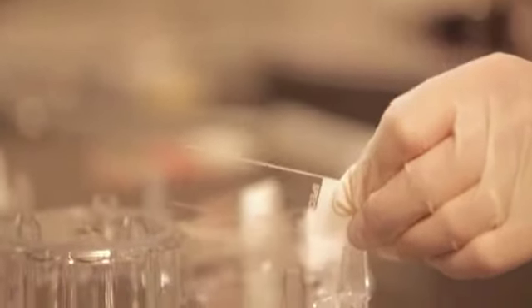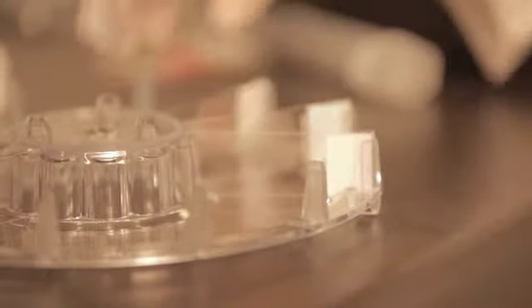The stainer can be programmed to conserve stains depending on the number of slides selected to be stained. The stain sprayed from each nozzle turns on and off for each selection of slides if 6 or fewer slides are selected to be stained. If all the positions are not filled with specimen slides, it is recommended to use blocking slides. Blocking slides are used so that each slide receives the same amount of stain. Without them, the first slide in the sequence of slides may stain slightly different than the slides behind it.